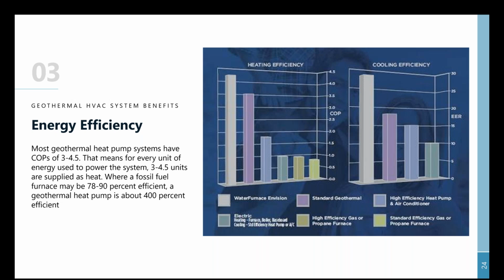This has always been the hallmark of a geothermal system, that it provides substantially better energy efficiency compared to traditional applications. Most geothermal heat pump systems have a COP, or coefficient of performance, between 3 and 4.5. That means for every unit of energy used to power the system, you get 3 to 4.5 units supplied as heat. Compare that to a fossil fuel furnace or boiler that may be 78 to 90% efficient, and a geothermal heat pump is about 400% efficient. So we're getting substantial benefit from an energy performance standpoint.